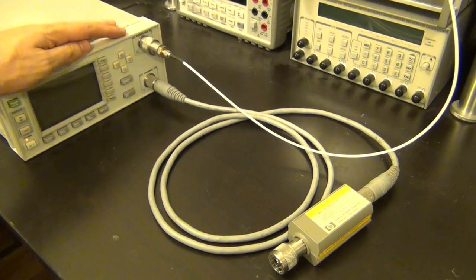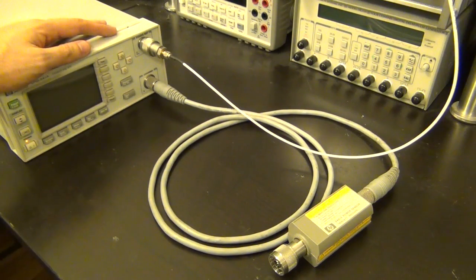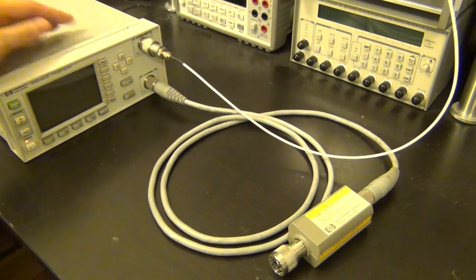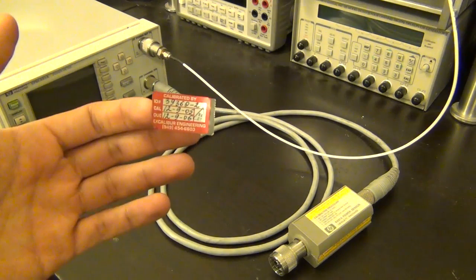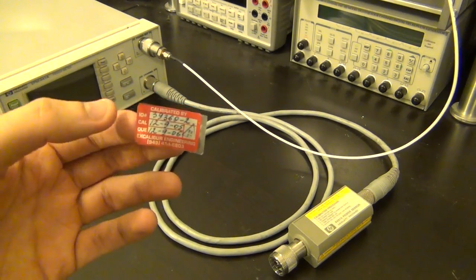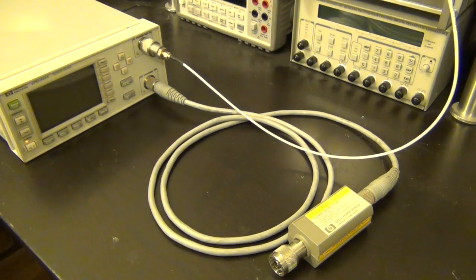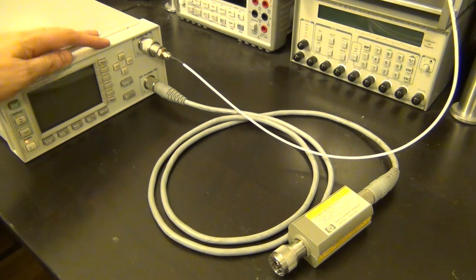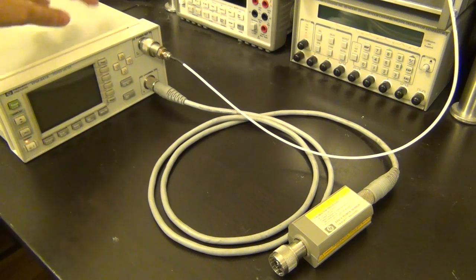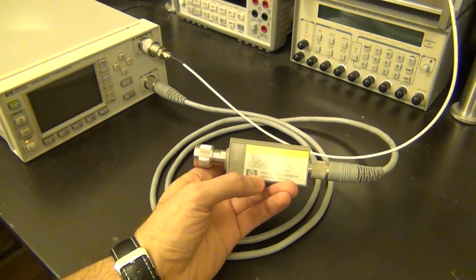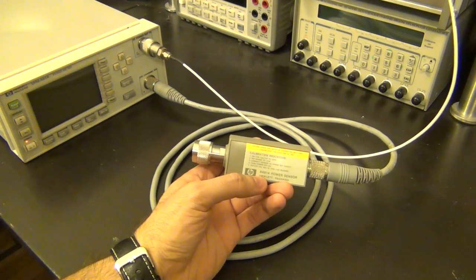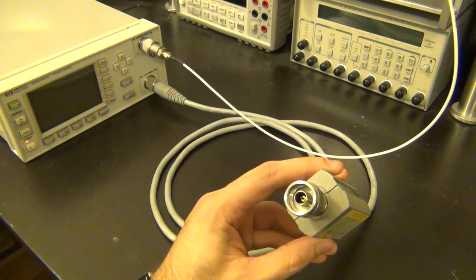Here we go, and I cleaned the unit front and back and everywhere. There's a lot of stuff on it, marking on it, and I also took the calibration sticker off, which was last calibrated in 2006. That's quite a long time ago, so I'm curious to see how well it is calibrated. And what I'm going to do is, I have actually connected to this power sensor, which I didn't show you earlier. It's a really old one. It's an HP-8481A, but it's in a very good shape.